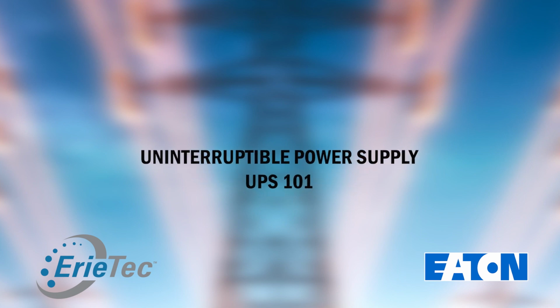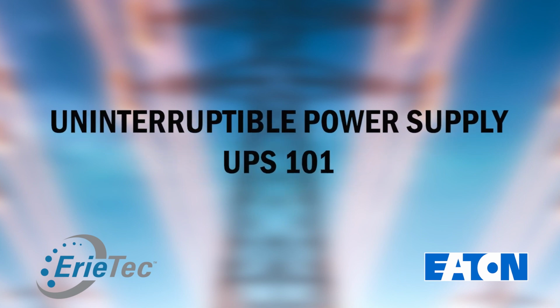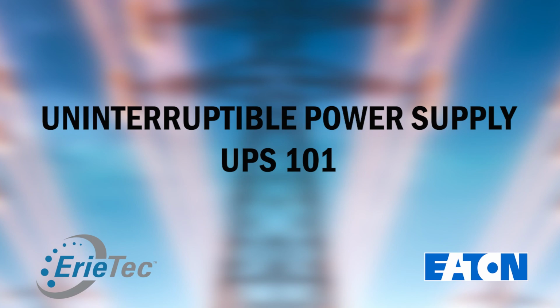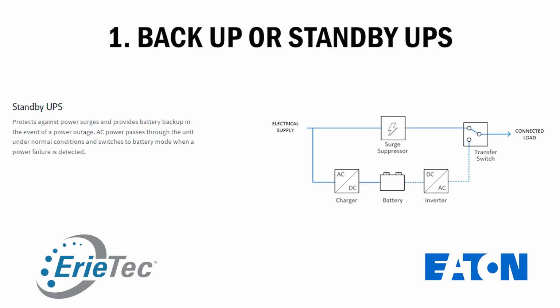What I would like to do to start is do a little bit of UPS 101. What is a UPS? How does it work? And what types are there? A UPS is an uninterruptible power supply. What it does is carry the load when the utility fails until either the generator kicks in, the utility comes back on, or you can have an organized shutdown of the equipment that is being backed up. There are three basic ways of accomplishing this inside of a UPS.